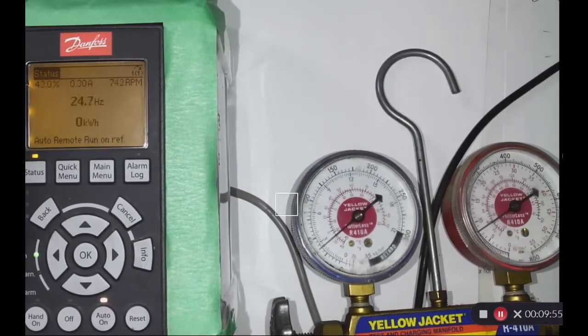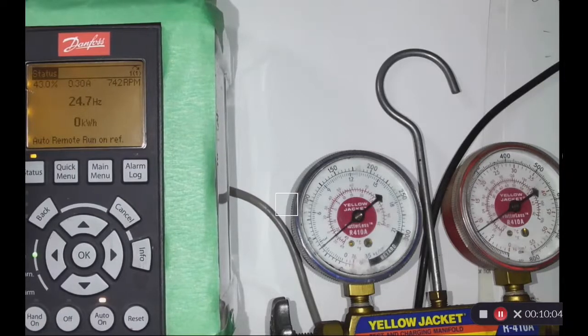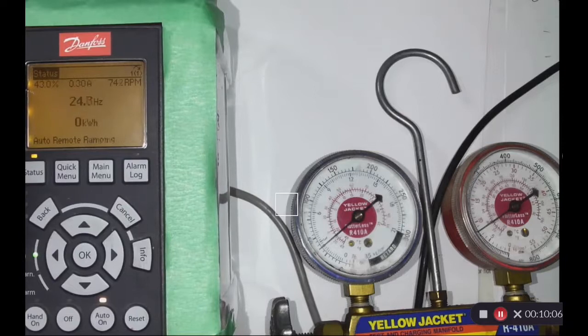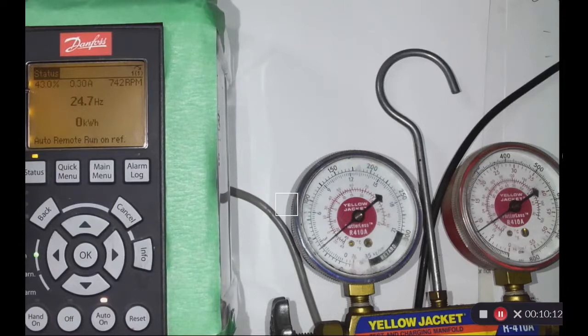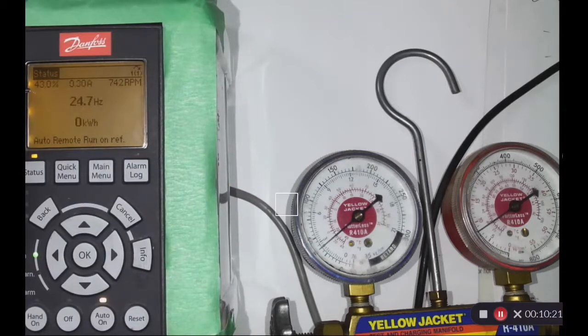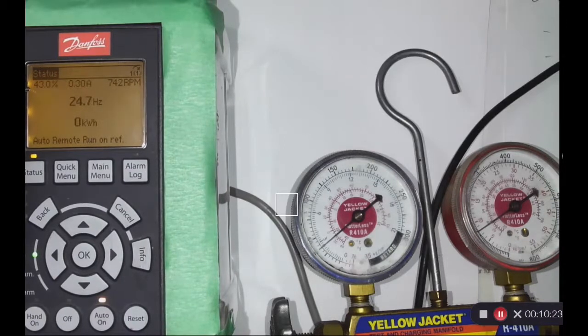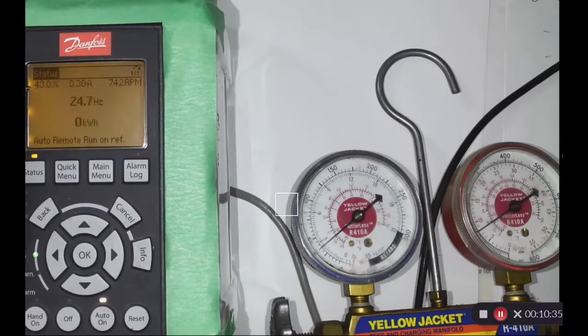And that's not reacting very fast because I have 10 seconds down, 10 seconds ramping down and ramping up. So that's why it's a little slower on the draw. You could have it a lot faster. I don't see a requirement for that. But like big fans, etc., you want to stay away from too fast a response for up or down, because obviously there's a lot of work going on and you could blow the brains out of the frequency drive if you asked it to control it down without brakes, etc., heater somewhere to deflect the excess energy that's coming back to the drive. This is obviously just a small application, so I'll just keep bleeding it off.